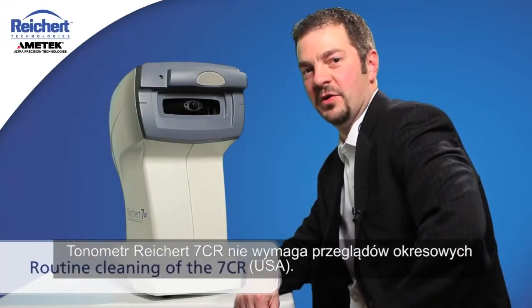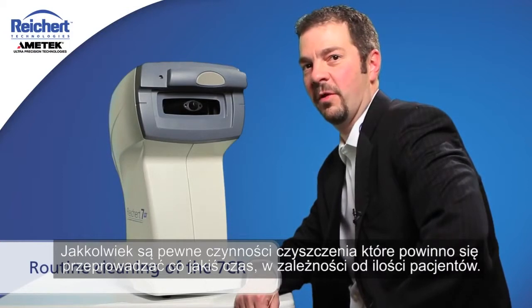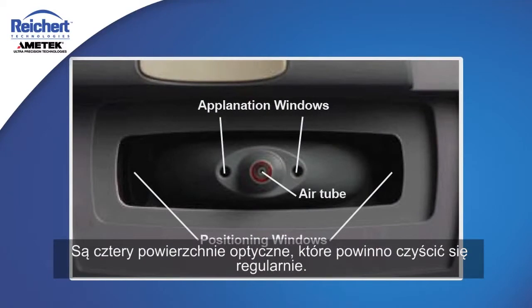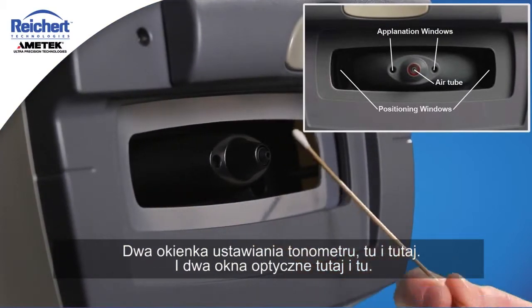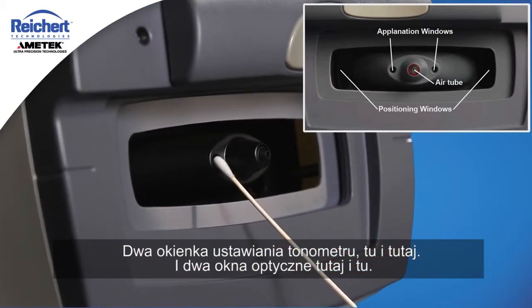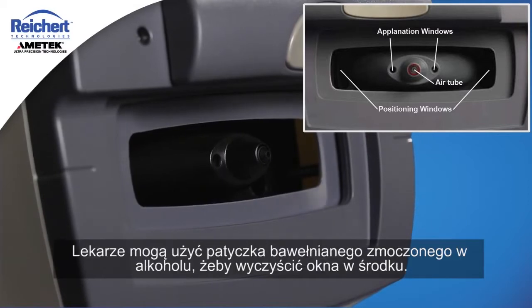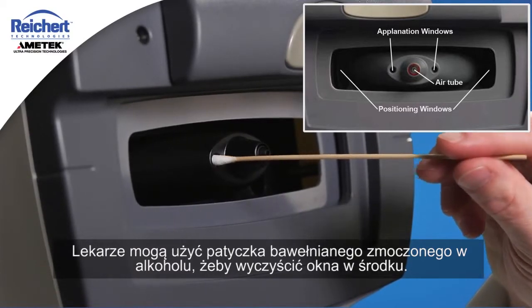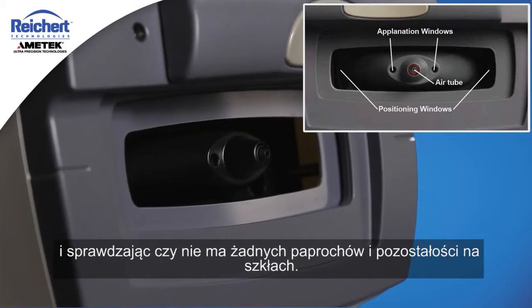The Reichert 7CR should not require routine maintenance. However, there are some basic cleaning tasks that should be performed on a semi-regular basis depending on patient volume. There are four optical surfaces that should be cleaned regularly — two alignment windows and two optical windows inside. Those windows are glass and can be cleaned with alcohol; clinicians can use a cotton swab lightly moistened with alcohol to clean the windows inside these holes.